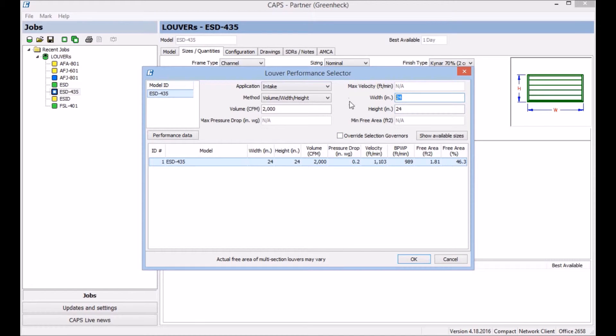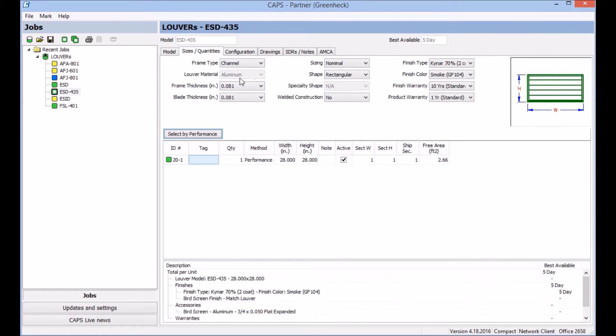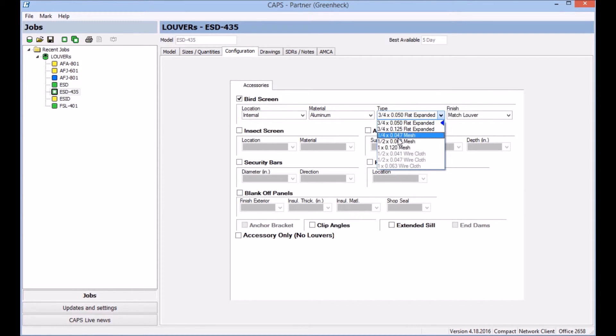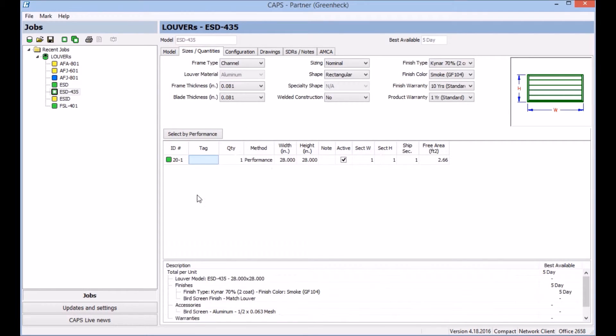I'm going to deselect that and scale up to 28 by 28. Now my pressure drop is lower — I like that. My velocity is right around where I want to be. Since my beginning point of water penetration is a little lower than 1000, it's in a pretty good area. My free area is also really high, which is good news. Here I can select different frame and blade thicknesses, welded construction, different colors — whatever you need is right there. Configuration, bird screen, insect screen — normally I see probably half-inch mesh bird screen. Then I'm going to tag this louver and move on to the next model.